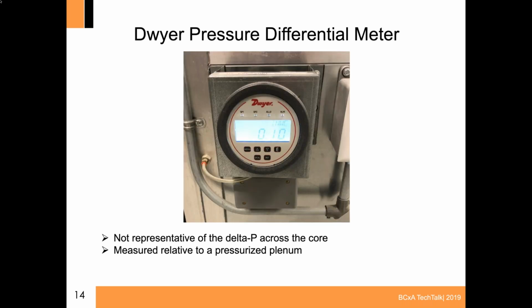Across the bottom core, where I showed you the picture of that energy recovery core, is a pressure differential meter. Unfortunately, this was not representative of what the actual pressure drop was across the core because it's not measured relative to the outdoor air. The air handling units are located on the roof of the schools and are connected to a stairwell. That's how you enter into it. And there's a very big plenum or access section attached to it for accessing the variable frequency drives and the motors and all of the access panels.